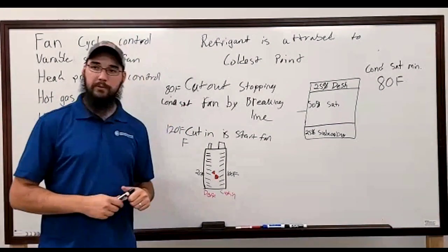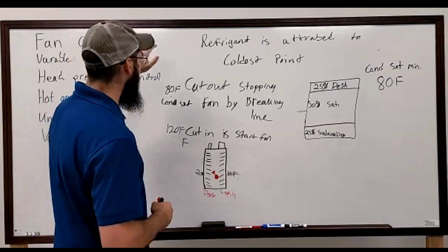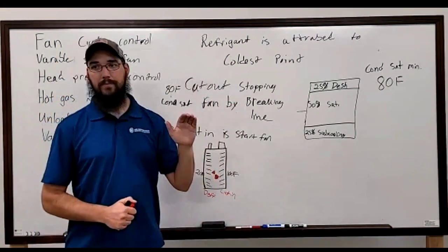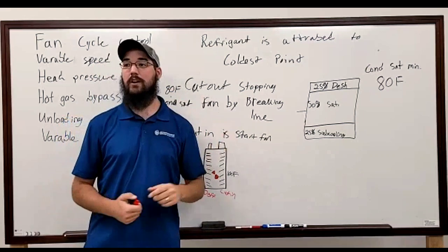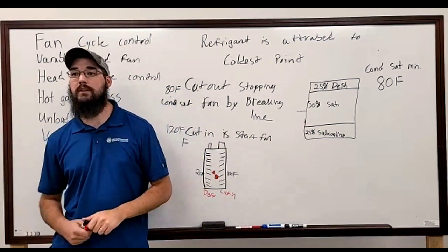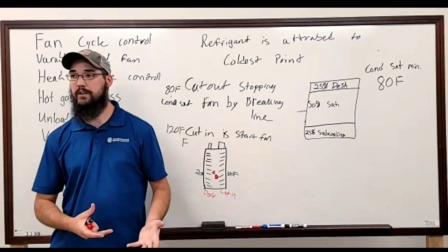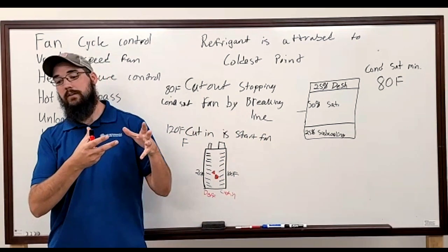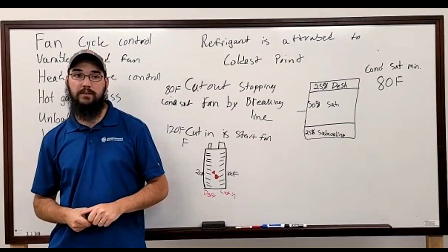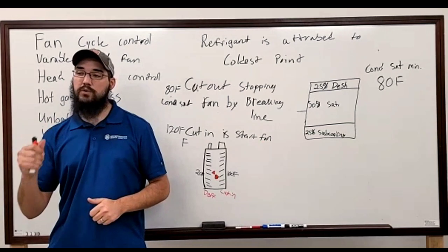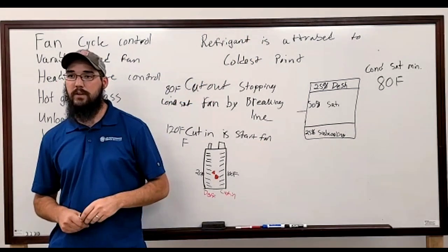There's a caveat that I want to warn you about, and it's only a matter of time before you see this when you are working on a heat pump system. Heat pumps, many times in our area, do actually still run cooling when it gets into low ambient conditions. I've had some heat pumps that have an office in a garage. That office stays warm even though it's 60 degrees outside. They're still trying to cool. In most circumstances, that's not a big deal. If the EXVs are inside, that's not too big of a deal.